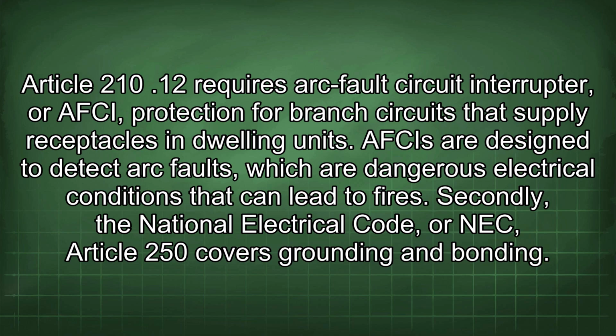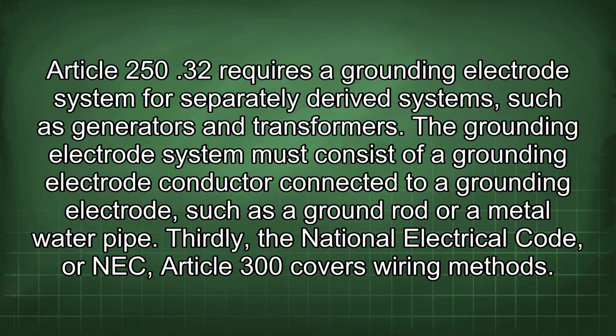Secondly, the National Electrical Code, or NEC, Article 250 covers grounding and bonding. Article 250.32 requires a grounding electrode system for separately derived systems such as generators and transformers. The grounding electrode system must consist of a grounding electrode conductor connected to a grounding electrode, such as a ground rod or a metal water pipe.